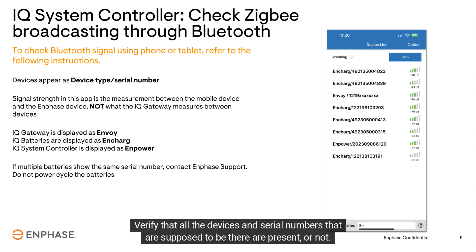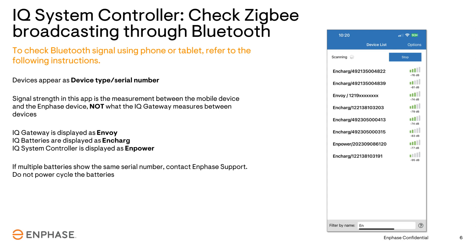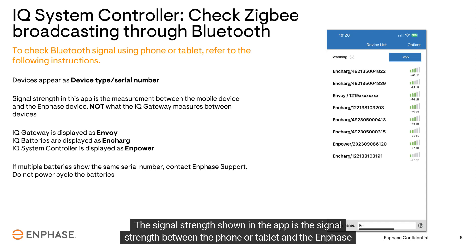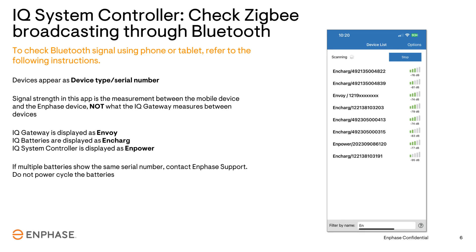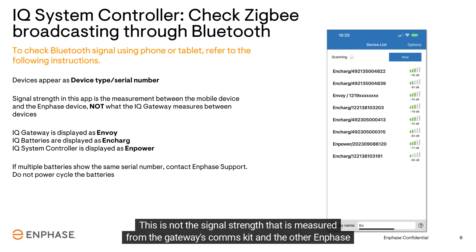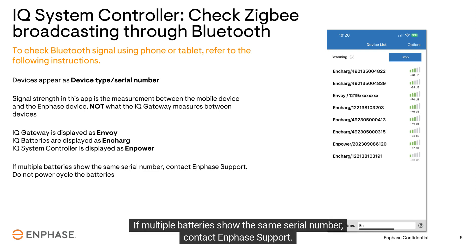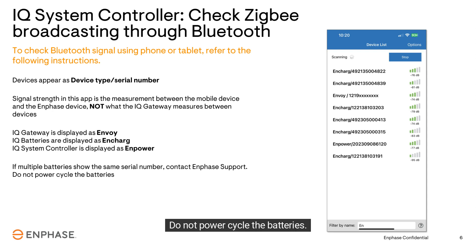Verify that all the devices and serial numbers that are supposed to be there are present. Also note the signal strength — the signal strength shown in the app is the signal strength between the phone or tablet and the Enphase device. This is not the signal strength measured from the gateway's comms kit to the other Enphase devices. If multiple batteries show the same serial number, contact Enphase support and do not power cycle the batteries.